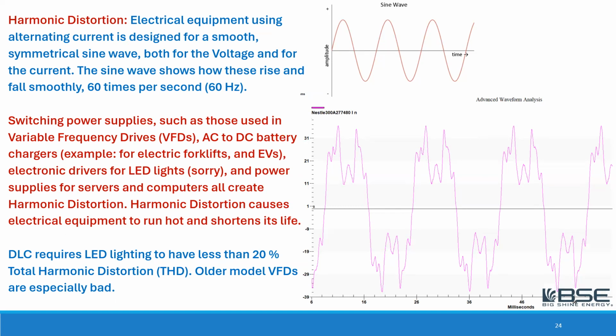Now, what causes the voltage and current waveforms to become distorted like that? Well, anytime we chop up the power and take AC and convert it to DC, or take DC and convert it back to AC, we're going to get harmonic distortion. Just about everything we do, there are so many different devices throughout our buildings, our plants, our laboratories, and our hospitals that are doing these things all day long. So keeping control of harmonic distortion is not easy, and it does have an effect on both our equipment and also the costs, as I showed earlier.